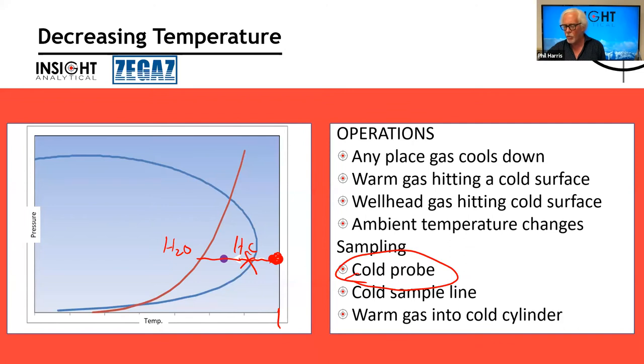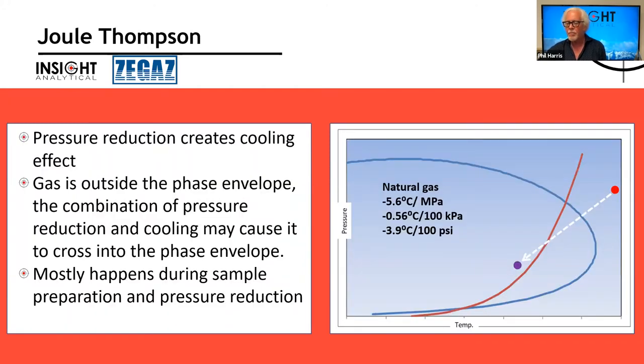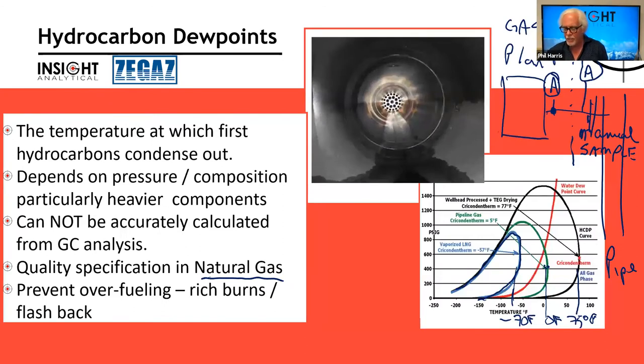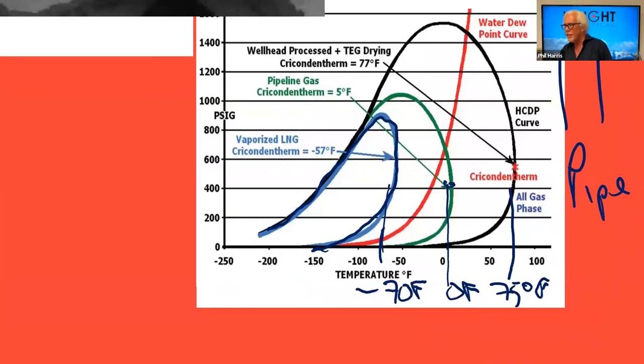It really does depend a lot on what the hydrocarbon composition is. So if I go back to, oops, wrong one. This graph at the bottom kind of shows that. You can see there's the water dew point curve in red. And if we're doing something like an LNG or a very high purity methane, the water dew point, if you started to cool the sample, so imagine cooling from the right to the left, you would hit the water dew point before you hit the LNG hydrocarbon dew point. If the sample was richer, like pipeline gas, it's potentially going to hit the hydrocarbon dew point before the water dew point. So you can't really put a number in there.